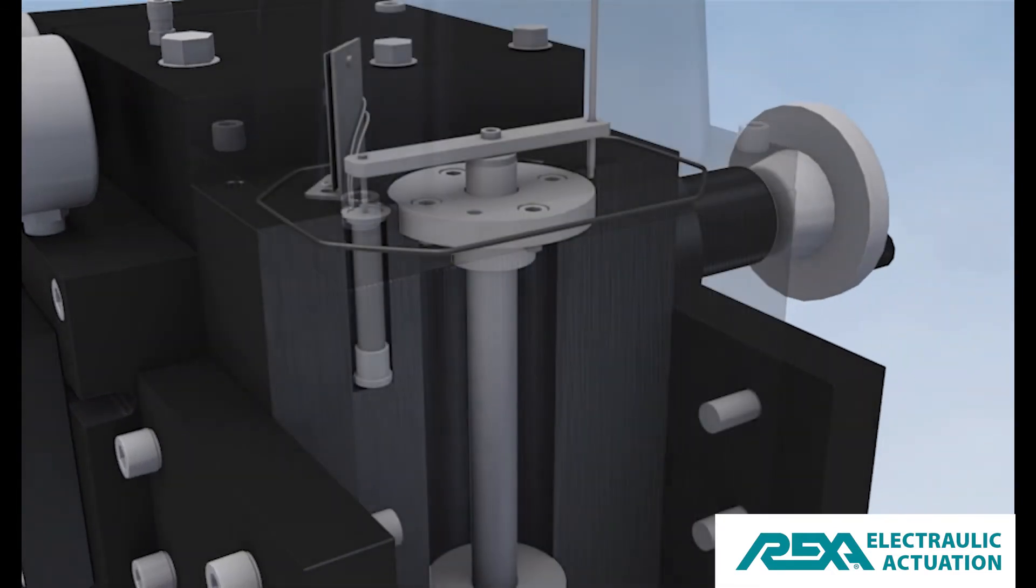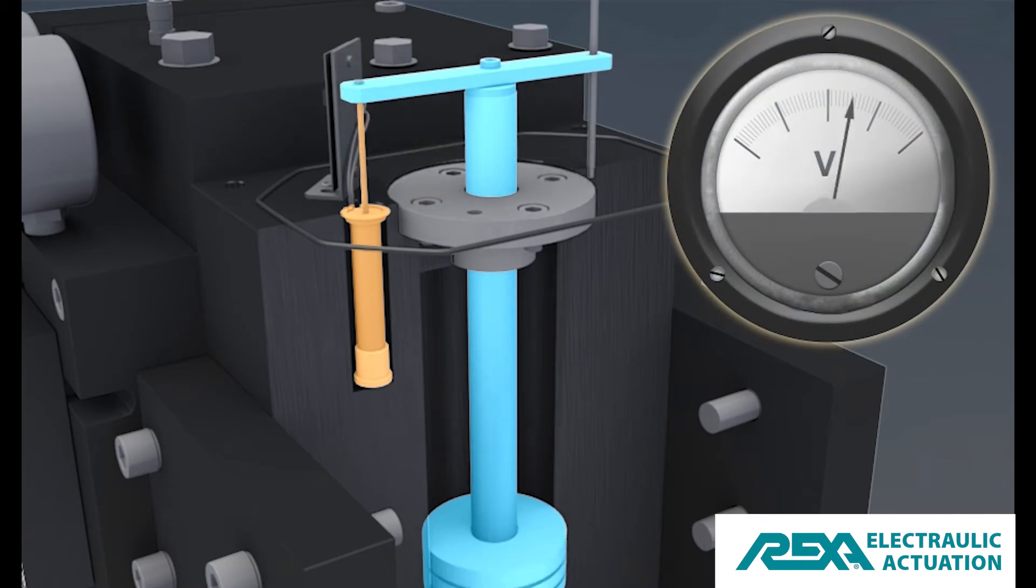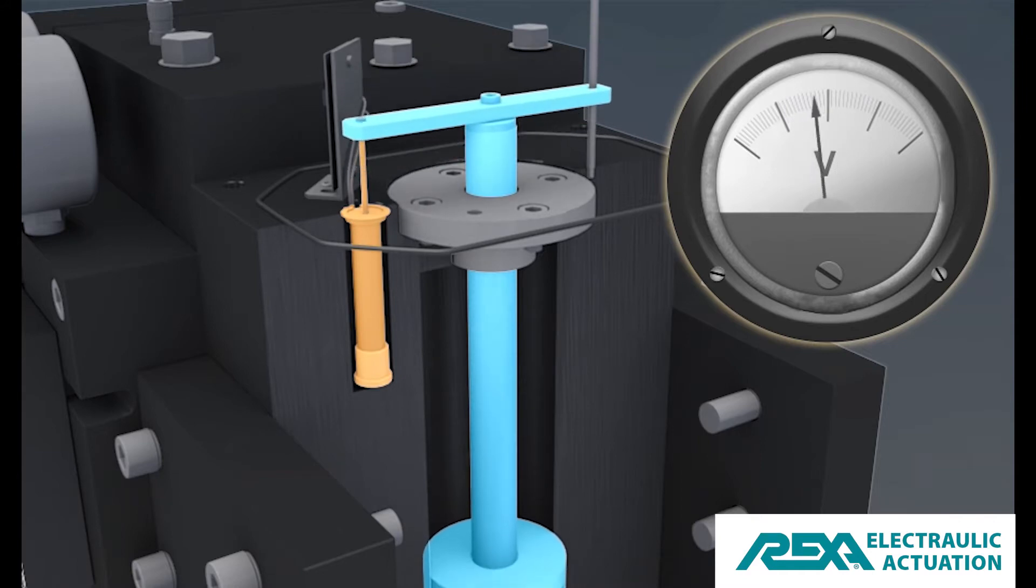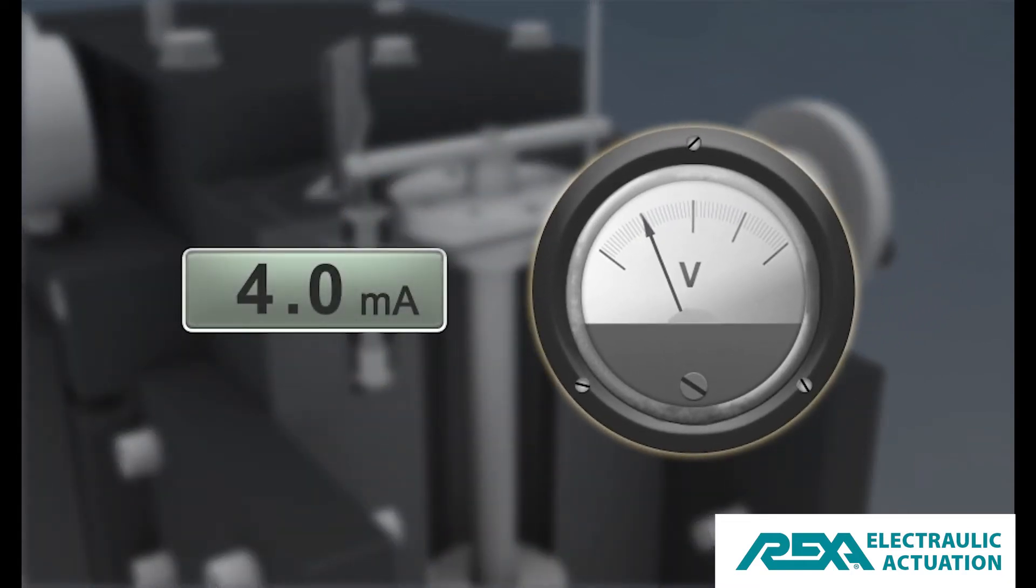The feedback module contains a potentiometer connected to the hydraulic cylinder. As the cylinder moves, it also moves the potentiometer, adjusting the signal from this device, which represents the position of the valve. The feedback board converts the potentiometer measurement to a 4 to 20 milliamp signal as the potentiometer changes position. The current will vary in relation to position.